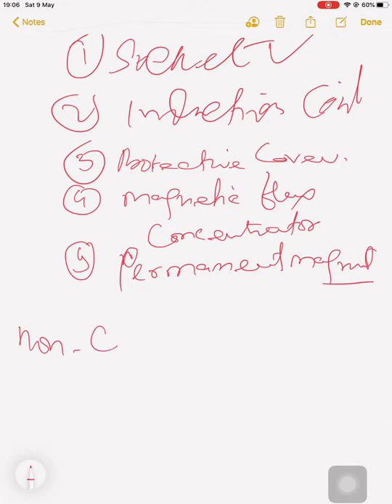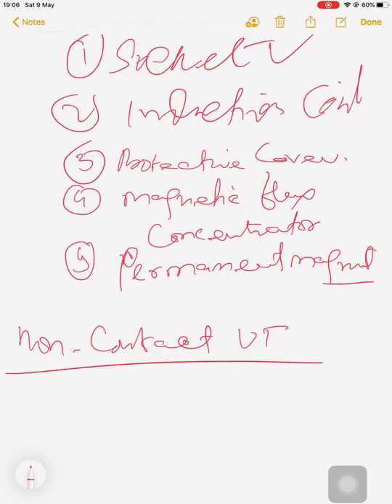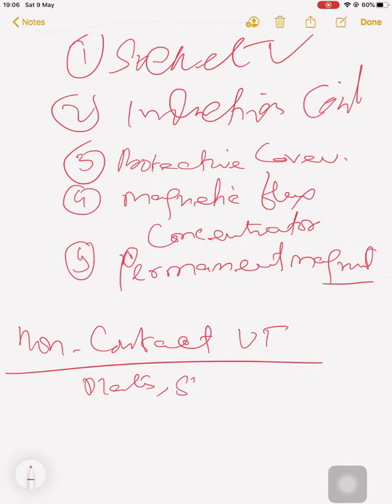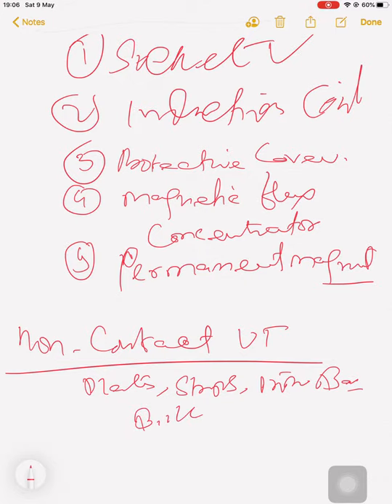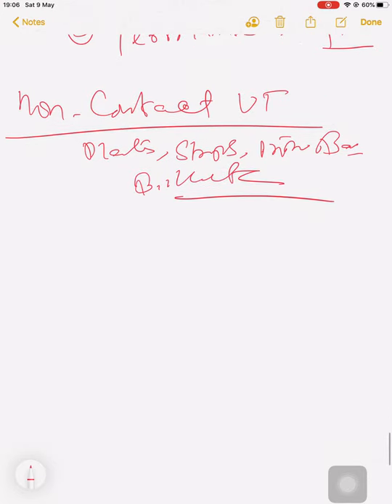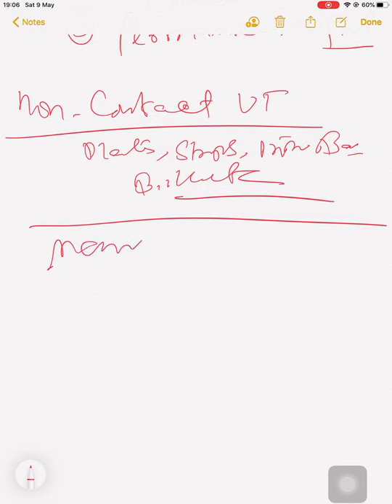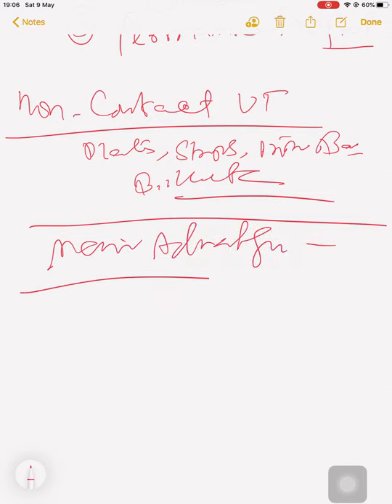So this all makes EMAT an extremely effective instrument for non-contact ultrasonic examinations. If you want to go for non-contact ultrasonic testing and that environment means you can test like your plates, strips, your pipe, your bar and your billets, etc. In that case, if you see the main advantage, I already told you main advantage of EMAT.